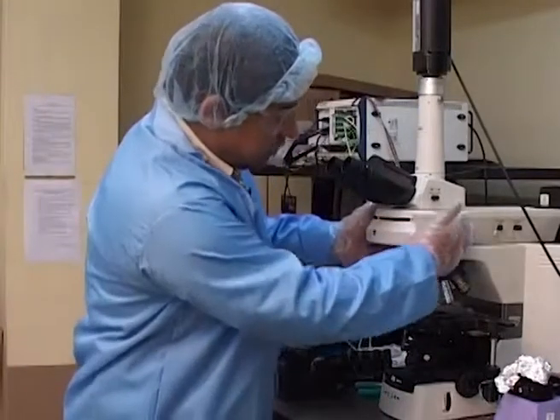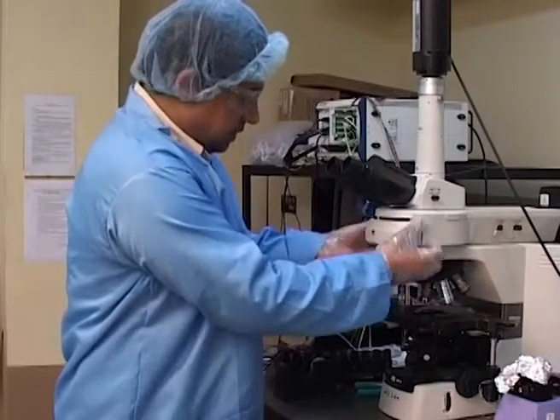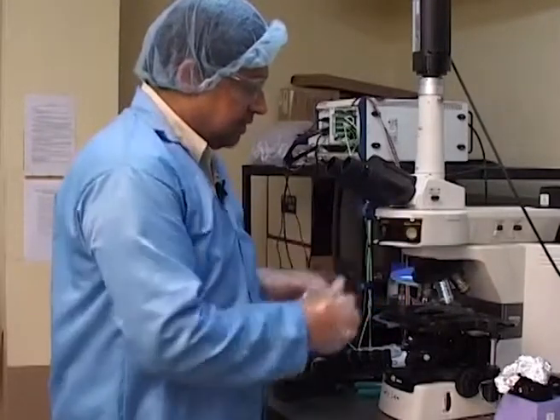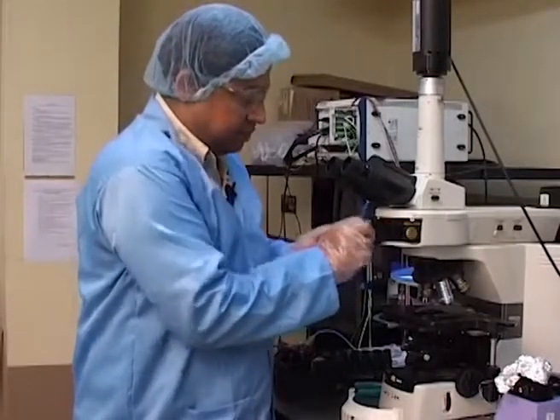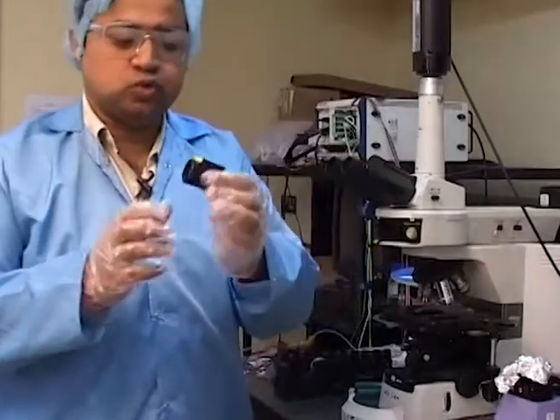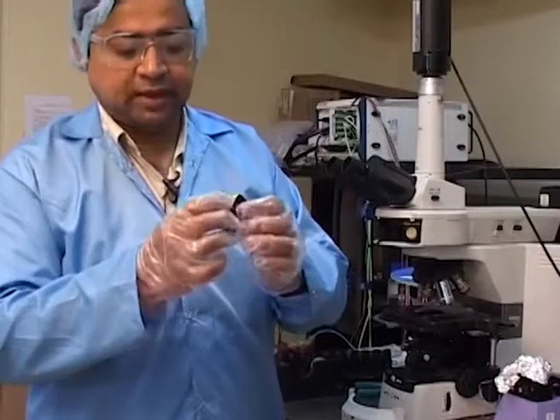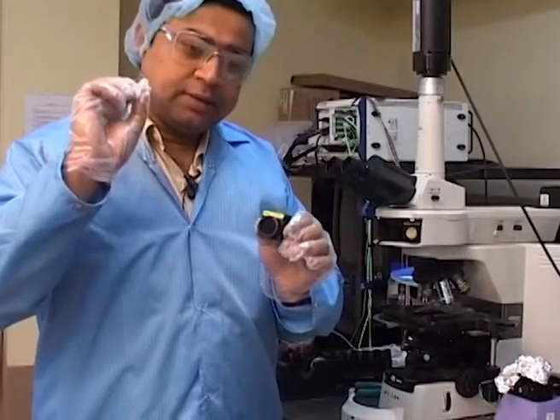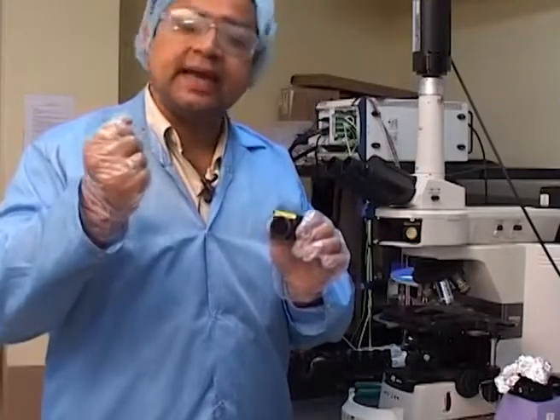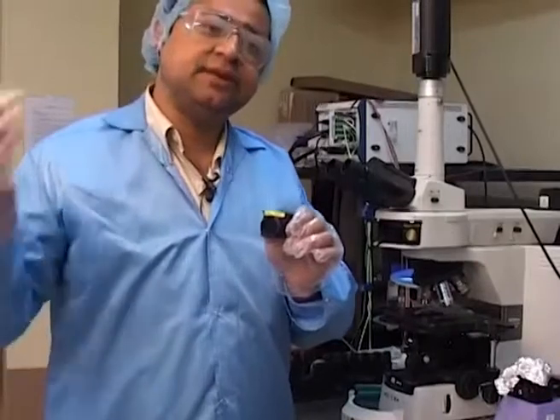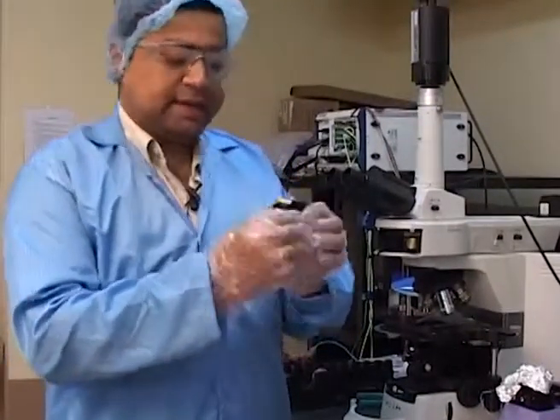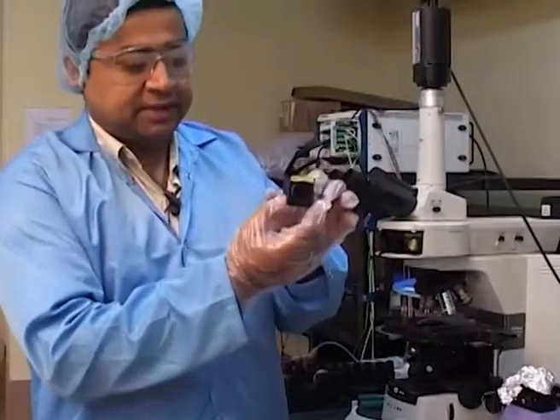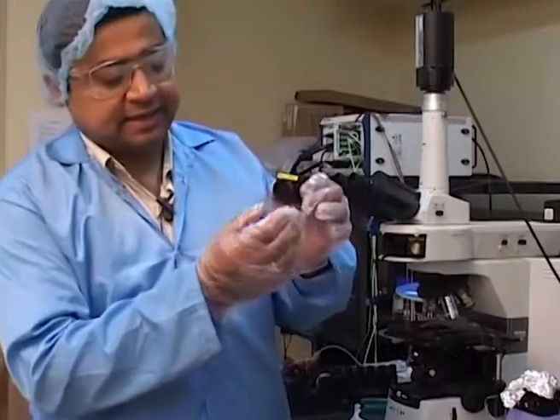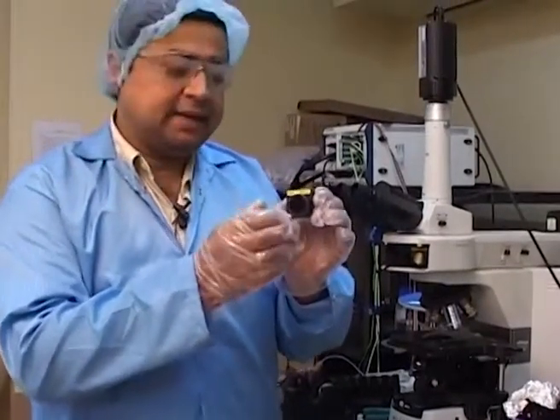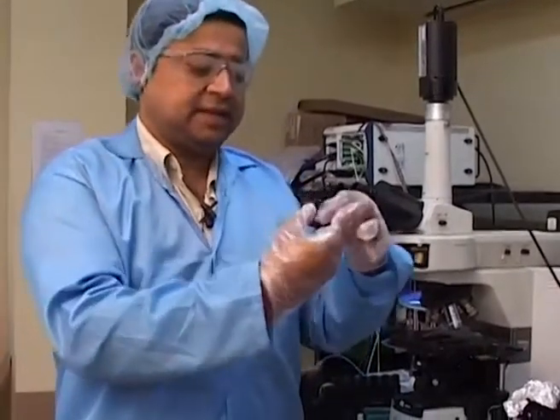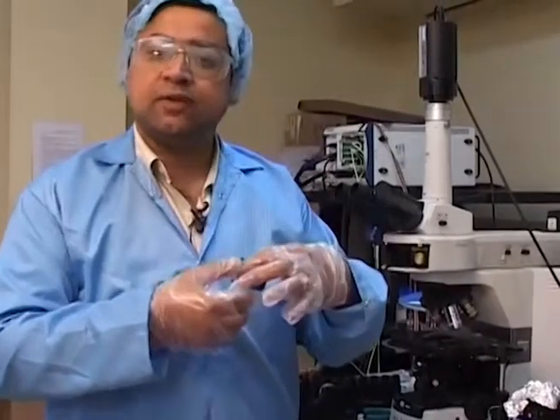So I'd like to explain what these filter cubes really do. Essentially, if you look at the way that the filter cubes are assembled, they are cubes which have two filters. What are filters? Filters are essentially pieces of glass which are designed to cut off certain frequencies and let certain frequencies of light go past it. So in this particular filter cube, as you see, there is an emission filter which is situated at the top. There is an excitation filter which is situated here, and then we have something called a dichroic mirror which is just placed in between this cube at a 45 degrees angle.